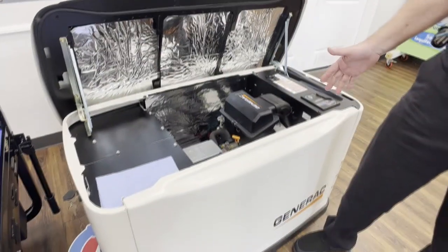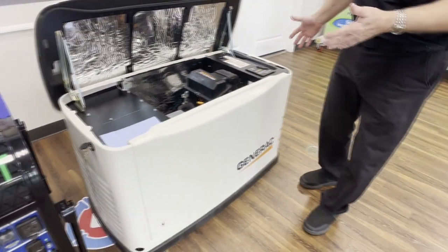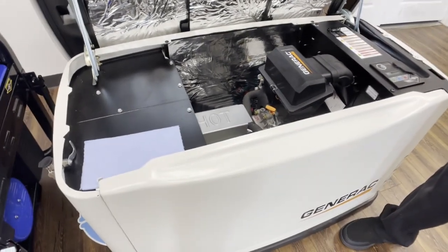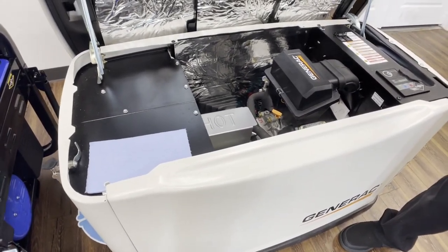And this is one of the best selling home standby generators. It's a 22 kW. Anywhere between 22 and 26 kW is what most people have that want to do their air conditioning if they want a permanently installed standby generator. And this is, as we have discussed, designed to be automatic. Yes, the automatic transfer switch will block the utility power when the power goes off and allow the generator to come on. And then do just the opposite when the utility power returns.